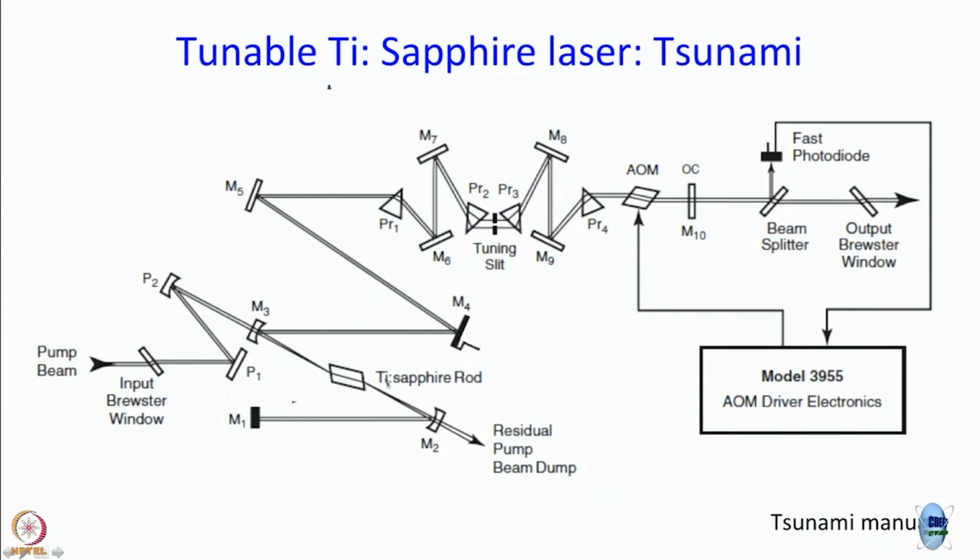So, you can see it on the card. Then you have to play around with controls of M1, so that it goes through this, right. Then this M1, M2 segment is aligned. You have to do the same thing here, because fluorescence that is captured by M2 has to retrace its path while going back to the crystal.